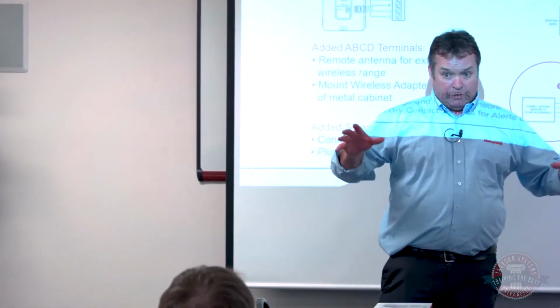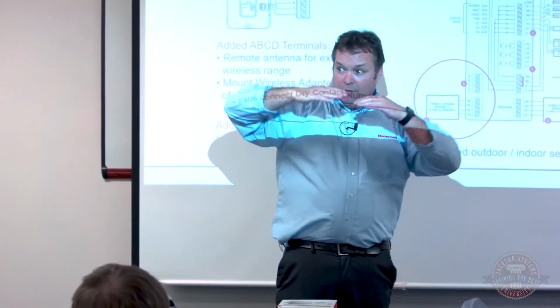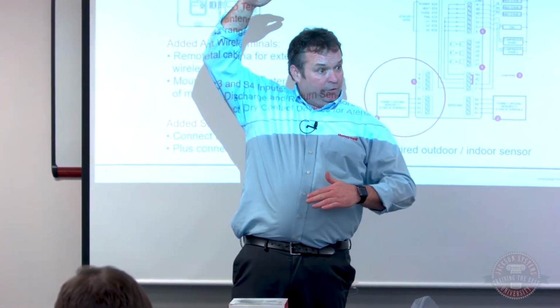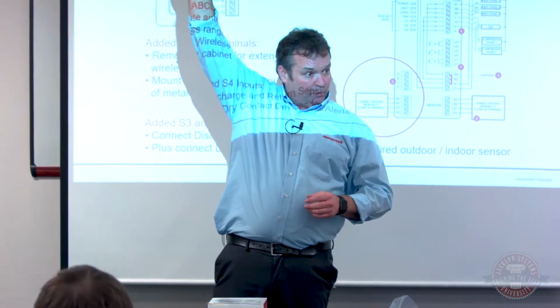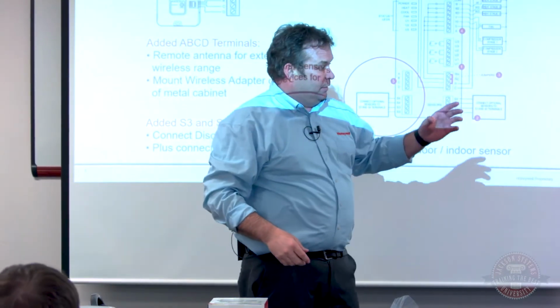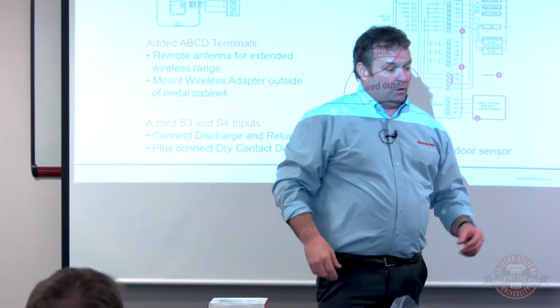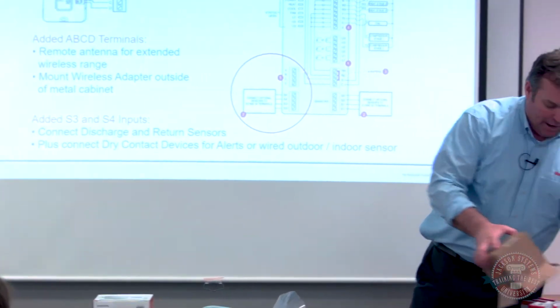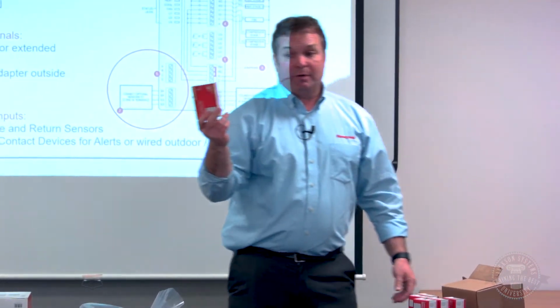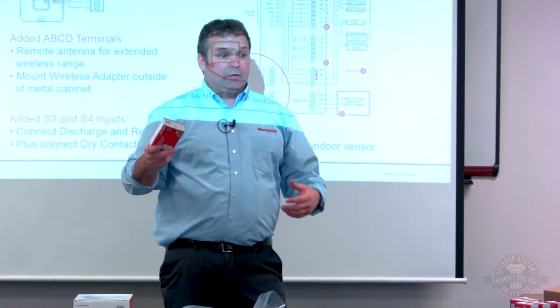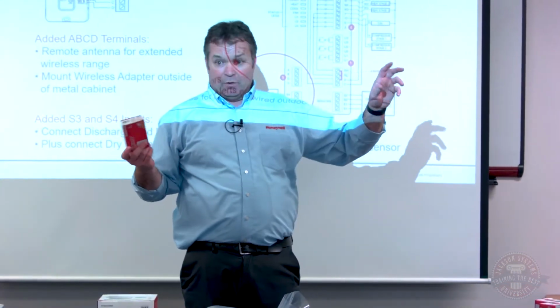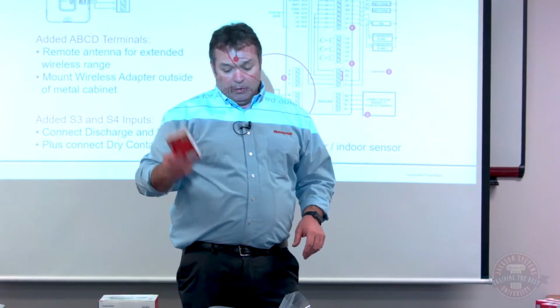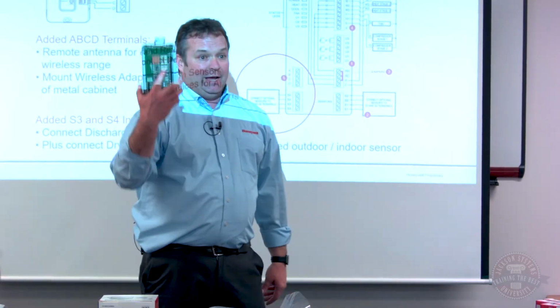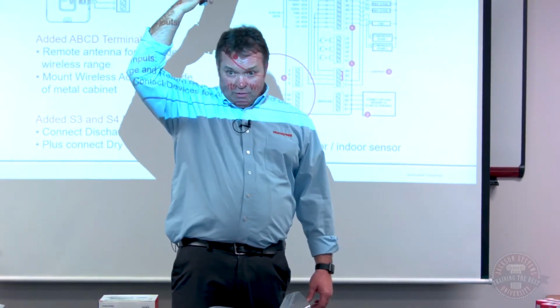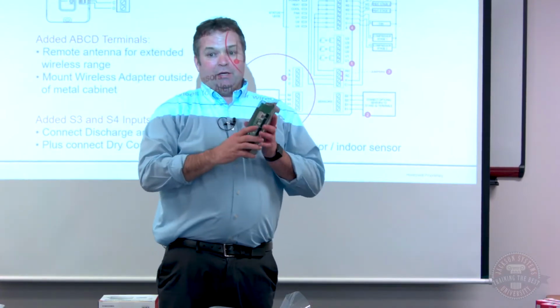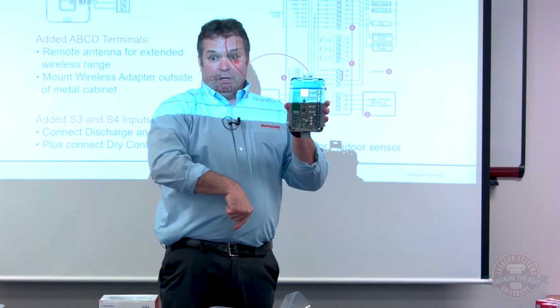Sometimes on commercial units, when you're doing a job with a big building and 30-foot ceilings, you've got package units up on the roof. You might want the thermostat in an office, but a wireless sensor out in the space to keep the employee from messing with the stat. Some people will put that sensor inside the package unit—you can do that, but you have to drop something below the ceiling line.